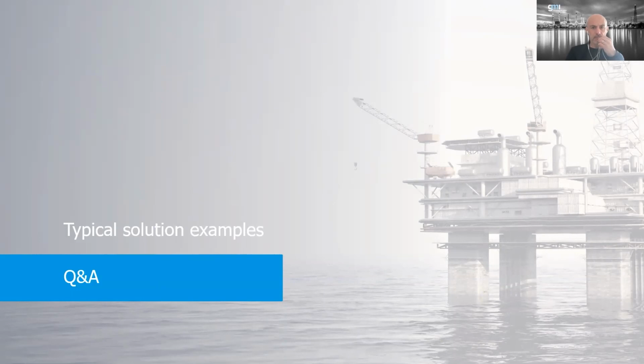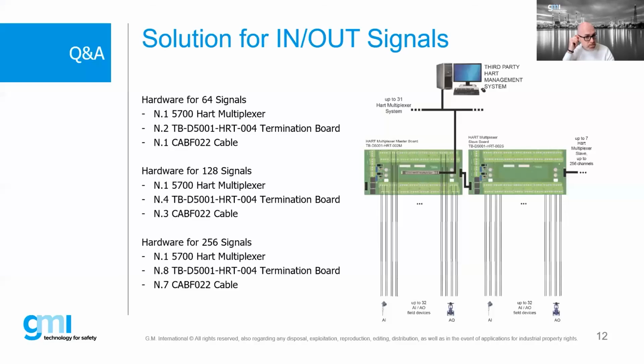Typical solution example. In the slide, we see some examples of application where the HART multiplexer is involved. Direct interfacing of 64 signals coming from the field, managed by 2 termination boards connected in daisy chain to each other with a single HART modem for channel scanning. The 2 termination boards are connected to each other through a special 10-pole flat cable, and this solution can be expanded up to the achievement of the direct management of 256 channels by a single HART modem, increasing the termination boards connected to each other in a daisy chain.